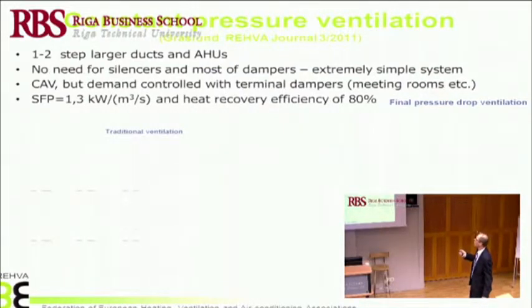This can be called final pressure drop ventilation, so that all the balancing is done with diffusers, which can also be ceiling beams, whatever type of supply air terminals. And for such a system, you really need one or two steps larger air handling unit, so it is really larger than this one, and you need larger ductworks to have very small pressure drops.